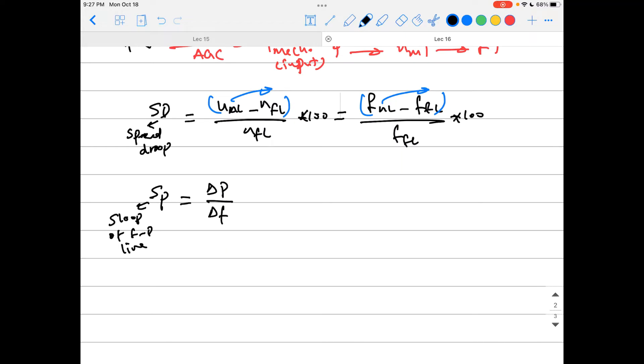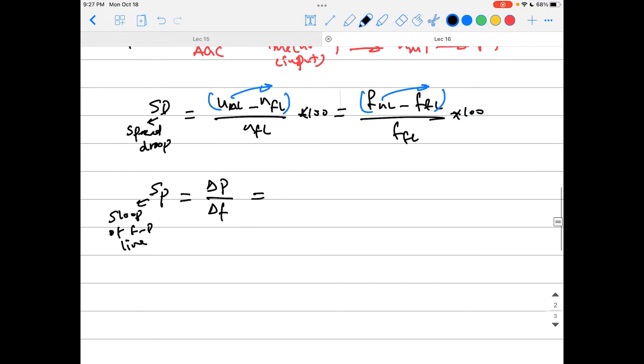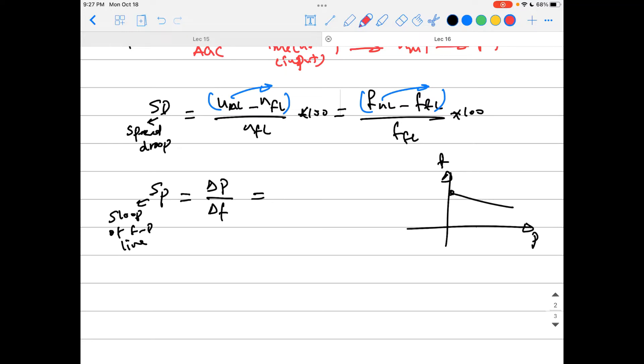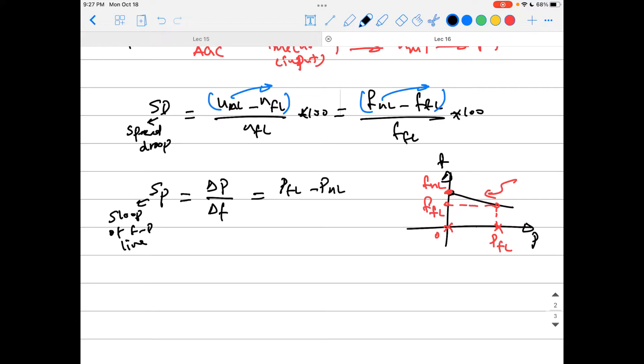Those relationships describe the isolated mode of generation — your generator connected to an isolated load. In isolated mode, you can allow the voltage and frequency to vary, as far as your load can handle it. Not all loads are sensitive to changes in voltage and frequency; resistive loads, for example, can tolerate some variation.